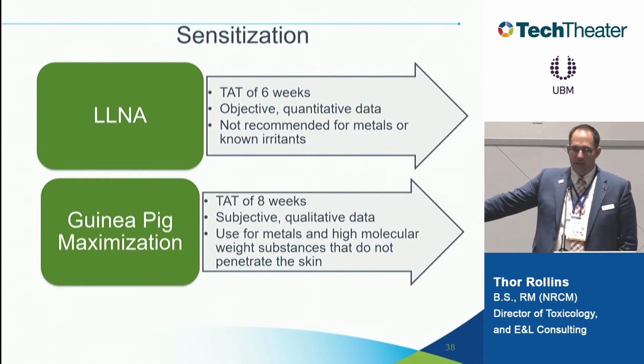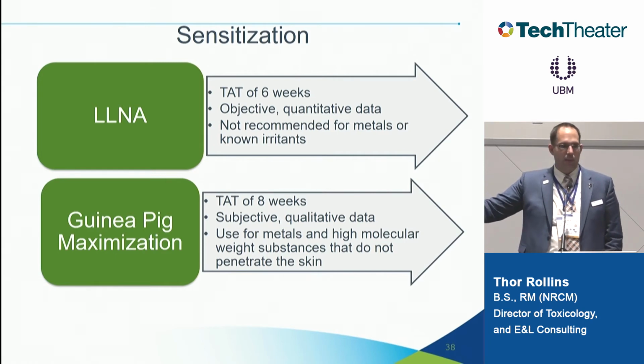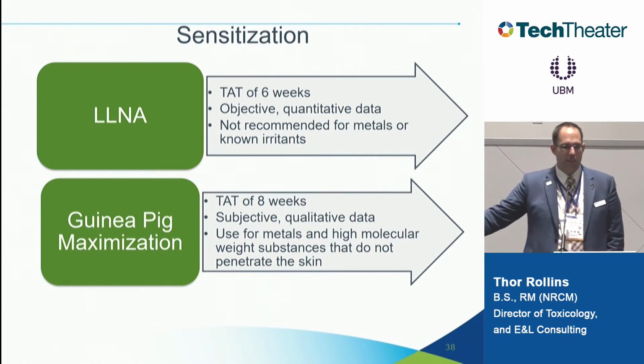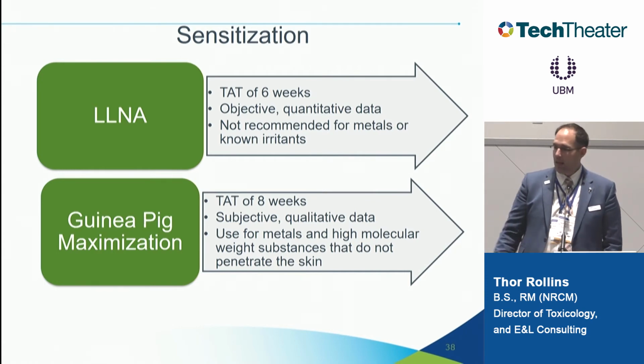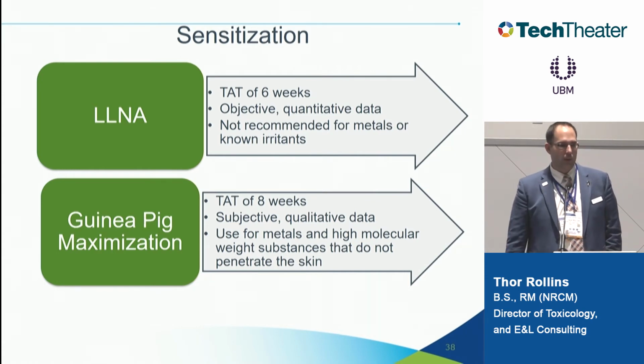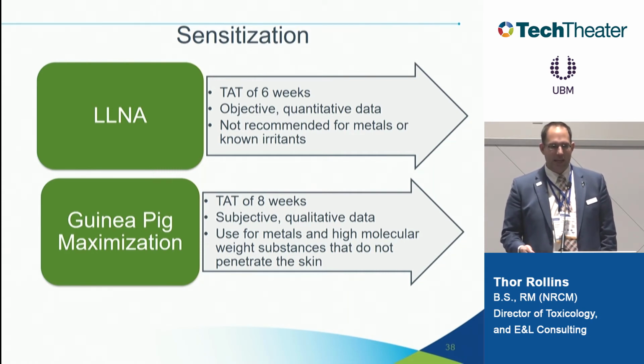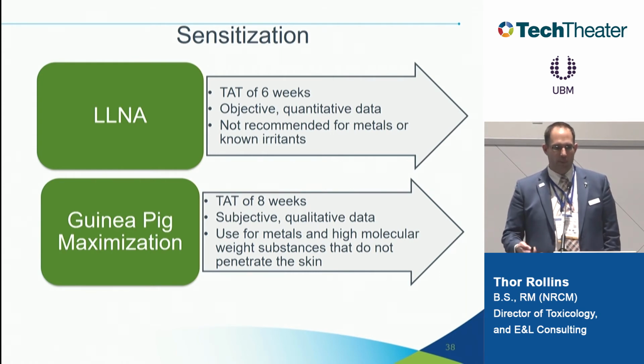These are 2 versions of the sensitization test. The only thing I'm going to say about them is that the LLNA is starting to become out. We're starting to not run LLNA because the FDA is not a big fan of it for most devices. So the guinea pig maximization is the most common one run. We are starting to be able to use chemistry to justify sensitization, but we're not quite there 100%.